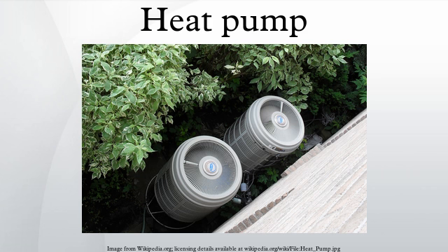Coefficient of performance and lift. The COP increases as the temperature difference, or lift, decreases between heat source and destination. The COP can be maximized at design time by choosing a heating system requiring only a low final water temperature, and by choosing a heat source with a high average temperature. Domestic hot water and conventional heating radiators require high water temperatures, reducing the COP that can be attained, and affecting the choice of heat pump technology.